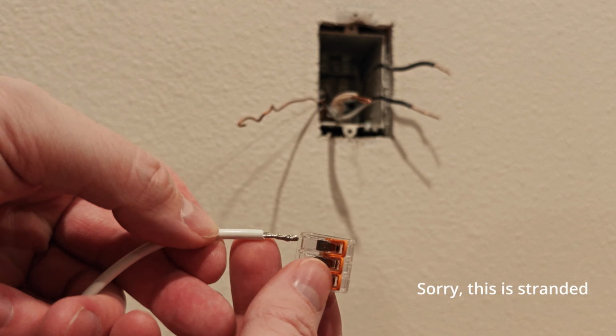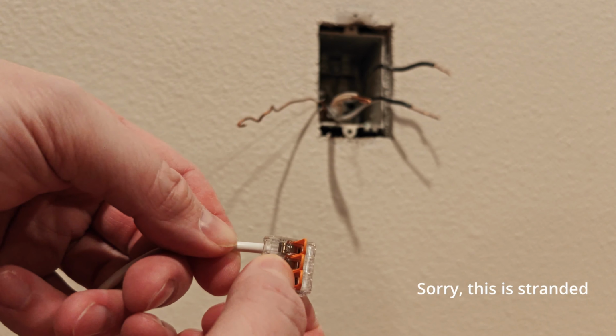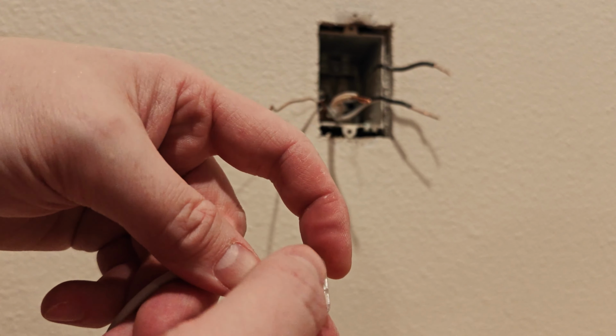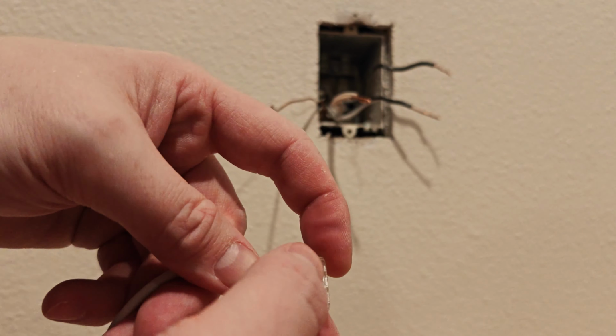Because we're going stranded to solid wire, I prefer using Wago connectors, in which case we'll flip up the tab and insert the solid wire all the way in until you can see the exposed copper at the end. Flip the tab back down and it'll snap in place. You can give the wire a tug to ensure that it's firmly seated. Next, you'll do the same for the stranded cable.